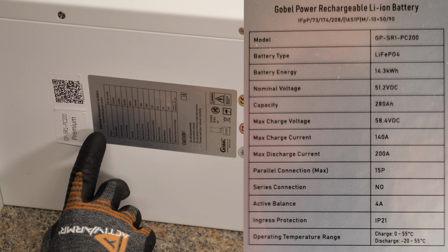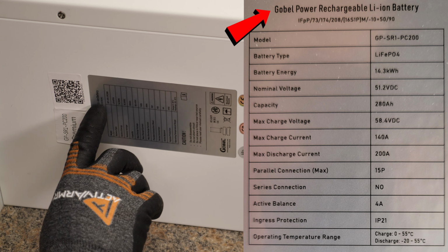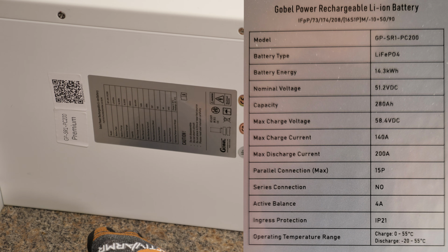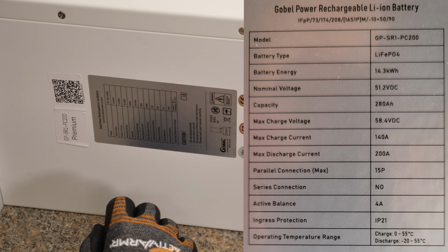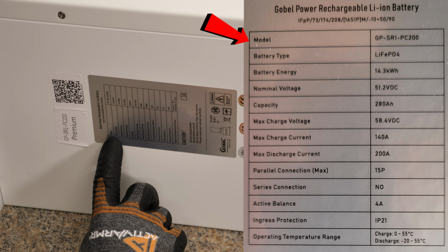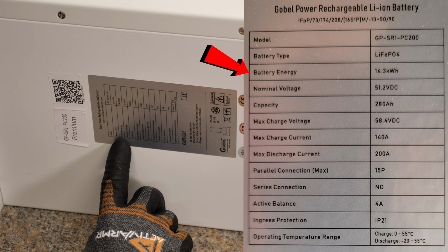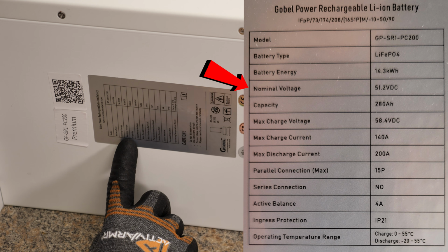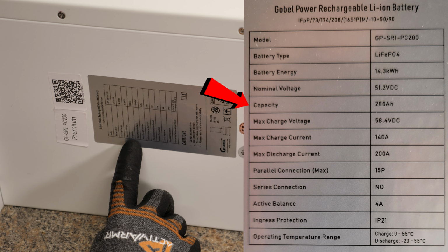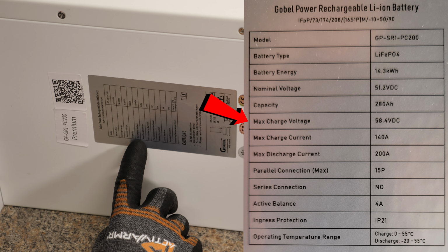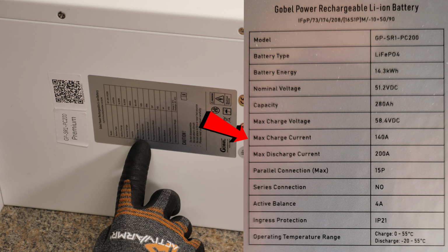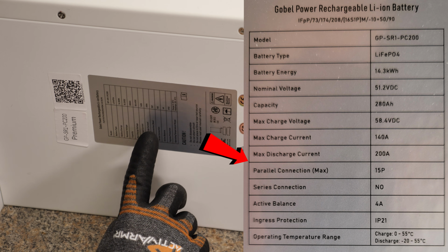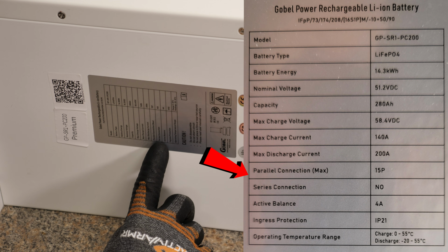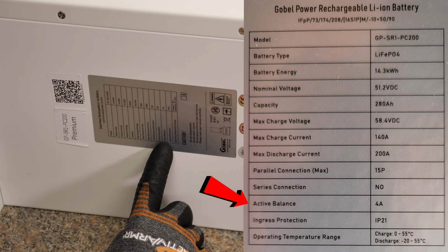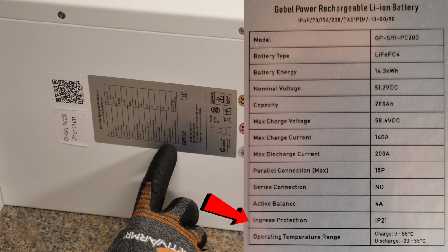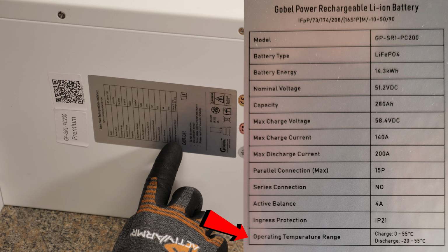All right, so if we go over the sticker right here, it says Gobel Power Rechargeable Lithium-Ion Battery, even though it's not a lithium-ion battery. I think that's just part of how it's supposed to be packaged and shipped. Anyway, model number is GP-SR1-PC200, which we already said. Battery energy is 14.3 kilowatt hour, nominal voltage 51.2 volts, capacity 280 amp hours. Maximum charge voltage is 58.4, max charge current is 140 amps. Max discharge current is 200 amps, and it looks like you can parallel up to 15 of these batteries. You cannot do a series connection, and it has a 4 amp balancer like we already mentioned, and the ingress protection is IP21, and then they've got your temperature ranges right here.